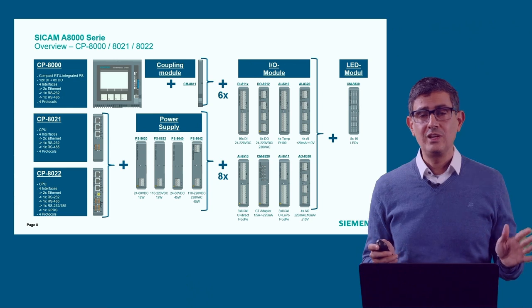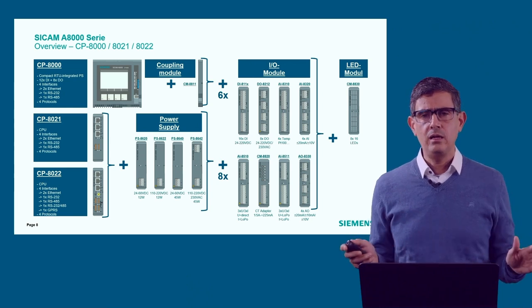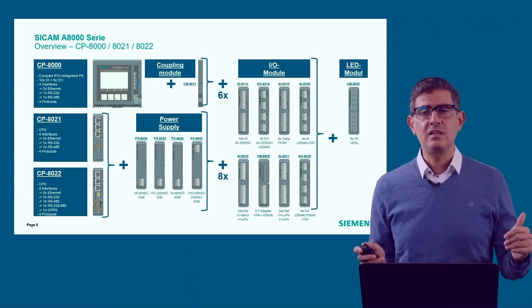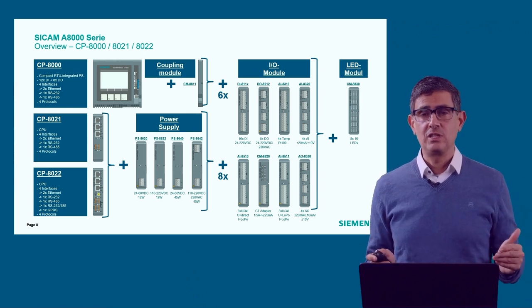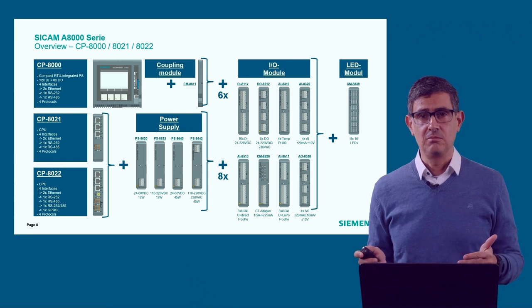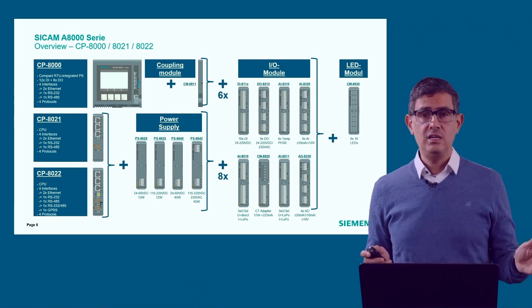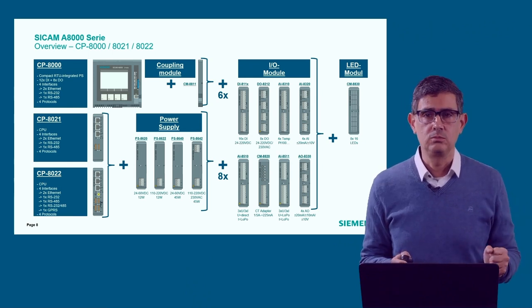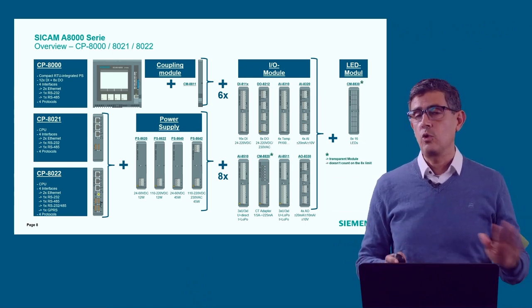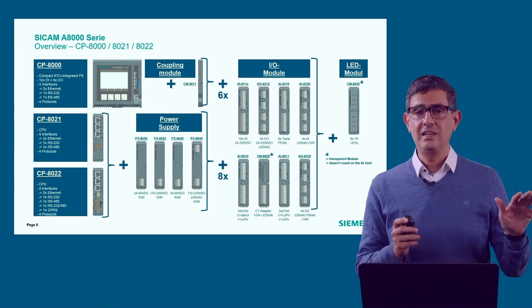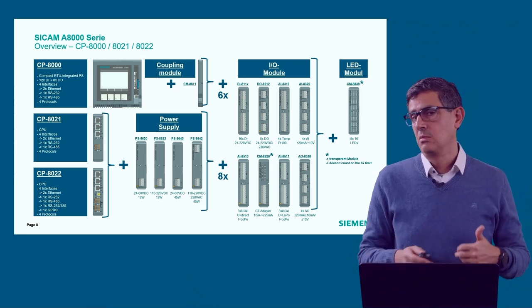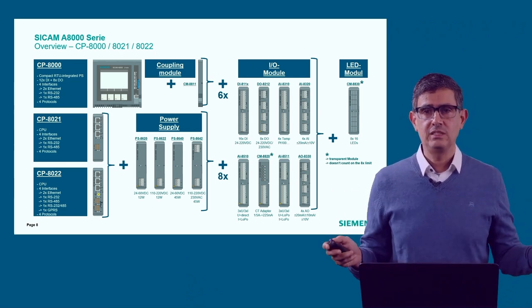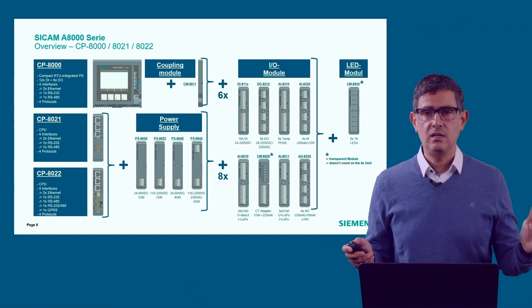Our RTUs are quite small so you can install them on any panel, but they can still have the inputs and outputs animated through LEDs. For that we have the LED module CM8830 — you just plug it in and it will automatically reflect the status of the inputs and outputs of your RTU. This module is not counted in the eight-module limit; it is a transparent module. For each group of eight modules you can have one of these modules animating all the statuses.